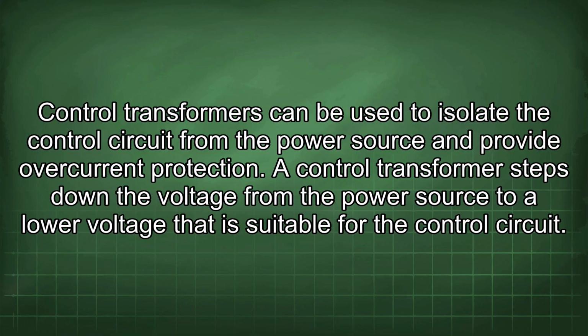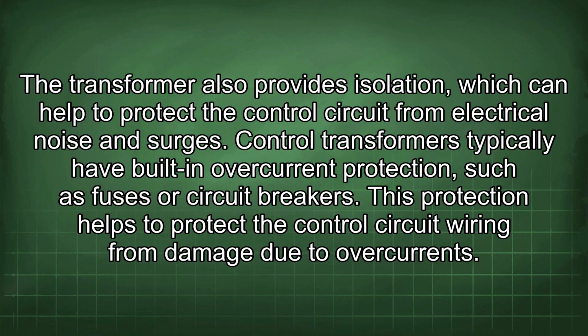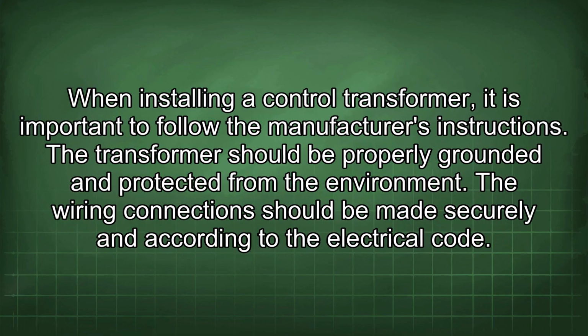A control transformer steps down the voltage from the power source to a low voltage that is suitable for the control circuit. The transformer also provides isolation, which can help to protect the control circuit from electrical noise and surges. Control transformers typically have built-in overcurrent protection, such as fuses or circuit breakers. This protection helps to protect the control circuit wiring from damage due to overcurrents. When installing a control transformer, it is important to follow the manufacturer's instructions. The transformer should be properly grounded and protected from the environment. The wiring connection should be made securely and according to the electrical code.